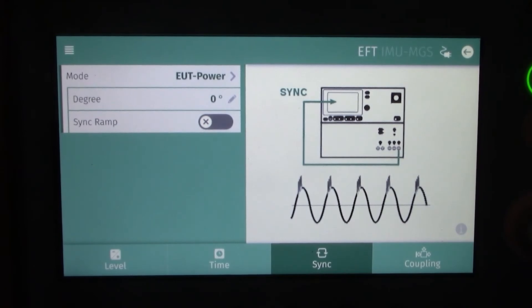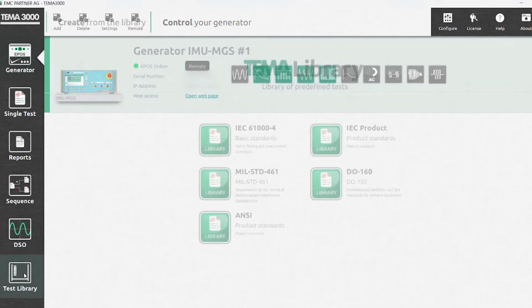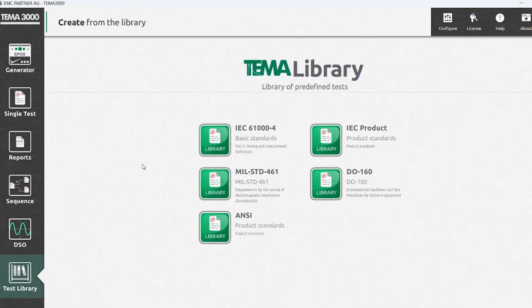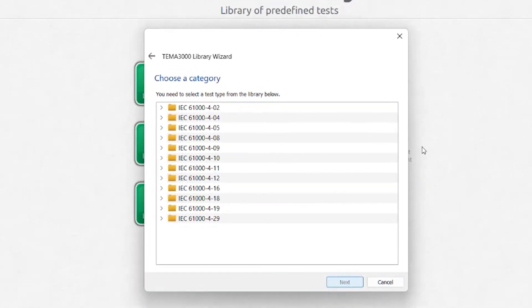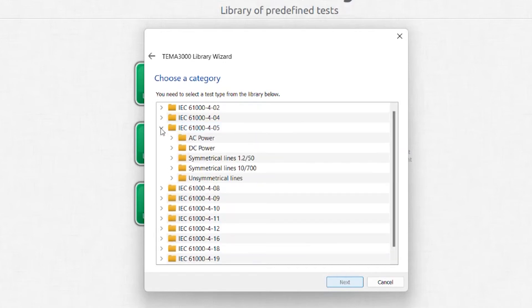Now let's plug in the laptop and get the EMC Partner TEMA 3000 software booted up. Along the left side of the software you'll see options for generator, single test, reports, sequence, DSO, and test library. Taking a look at the test library, you'll find a series of pre-programmed standards available. Let's look at the IEC 61000-4 series, specifically IEC 61000-4-5 since that's what our generator is configured for. The test library helps you select criteria in relation to what the standard indicates.